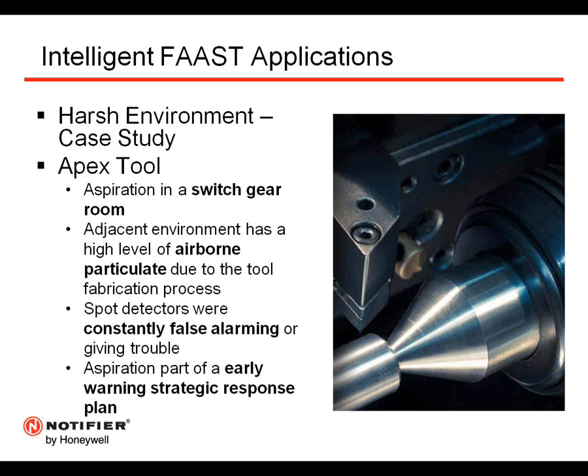They instigated a strategic response level so that if they did get an alarm from the FAAST device, the security guard would go and make sure that it was indeed a fire in the area instead of a nuisance alarm. One day they actually did have an issue out on the production floor, and that smoke seeped from the production floor into the switchgear room and initiated an alert at the FAAST. As the guard was walking out to that switchgear room to investigate, he saw that there was an incident on the production floor, verified that there was no issue in the switchgear room, and as a result, they were able to keep production up and running.